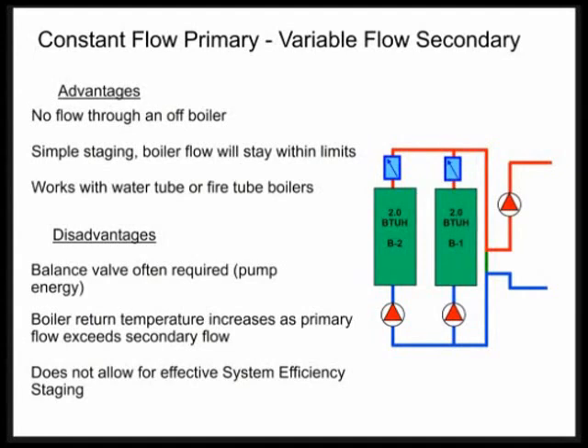Now, what are some of the disadvantages? Well, you definitely have to have a balance valve. Well, you should. Some way to balance flow across the boiler. A lot of people use a balance valve and if you do, that's some pump energy. Also, the boiler return temperature increasing as the primary exceeds secondary, which is going to happen a fair amount of the time. Again, it's not the end of the world. It's how it's designed, but you will get some return water temperature fluctuation. Definitely a disadvantage being that it doesn't allow for effective system efficiency staging, at least in your typical HVAC system. Remember, water source heat pumps still work fairly well in this area.